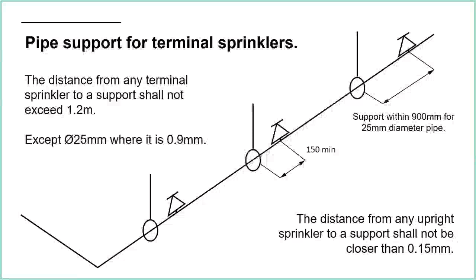Terminal sprinklers. Terminal sprinklers are where it's only supported on one side. So we're talking about coming off a distribution pipe, and it's only going in one direction. The distance from any terminal sprinkler to a support shall not exceed 1.2 meters, except 25 millimeters where it's 0.9. Again, I don't like this about our rules; for me, it'd be easier just to have one rule for all pipe sizes, rather than always having this. Well, it's like this, apart from this size, when it's like that. But that's where we're at anyway.